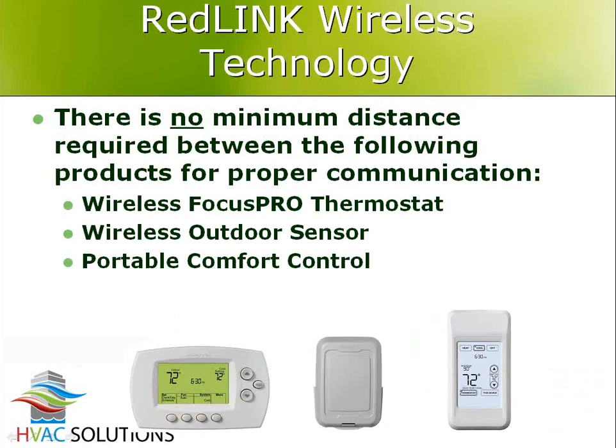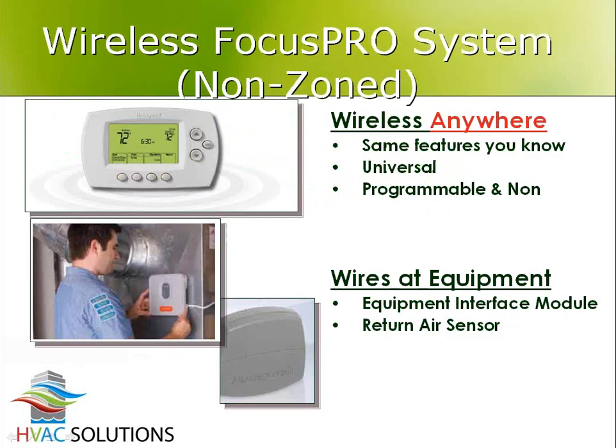Some devices don't have a minimum distance requirement between them. One of them is the Portable Comfort Control, which is the bottom right-hand picture over there. We'll talk about that in a little bit. That's a mobile device that you walk around with. It does not have any minimum requirements, so if you're standing next to the thermostat for some reason, it's not going to be an issue. The outside air sensor does not have an issue, and the FocusPRO battery-powered wireless stat does not have an issue. But for the most part, 2 feet. So on the equipment side, it's usually 2 feet minimum.